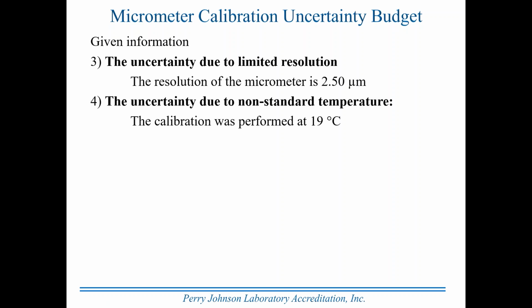The uncertainty due to non-standard temperature. The calibration was performed at 19 degrees C. For scientific and technical purposes, 20 degrees C is considered standard temperature. If you report dimensional values, size of a gauge block, size of a gauge pin, whatever, at any temperature other than 20 degrees C, it's necessary to calculate the variation due to the coefficient of thermal expansion and correct the result as a result. You either have to report the temperature at which you perform the calibration so the user can correct it for temperature, or you have to make the correction and report that as the result. We'll talk further about thermal coefficient of expansion. 12 micrometers per meter per degree C for the material that we're looking at here, the steel of the micrometer and the steel of the gauge block.